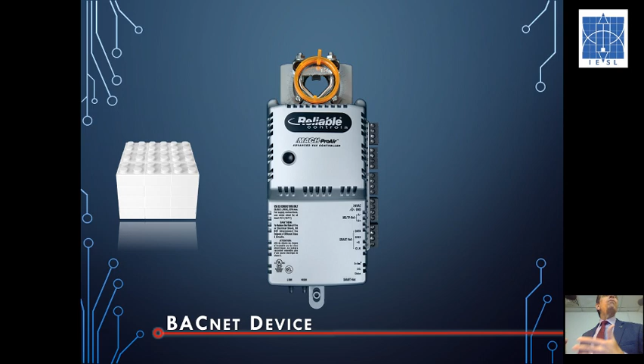Okay? And the purpose of a device is to transport information. Its existence is as a logical node, or a device that will reside on a BACnet network. This is a typical device that, if you're involved in BMS or mechanical systems, you probably have seen many devices that reside on a network. A device is actually identified by a composite three-piece number. The first part is what we call the device instance, and the device instance can be anywhere between 0 to 4,194,302, which means that BACnet has been purpose-built for a very large system.